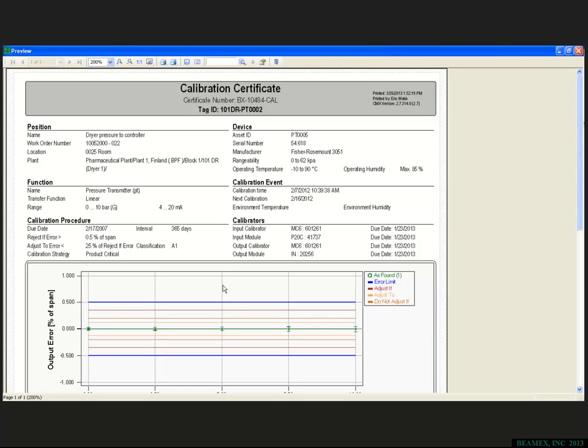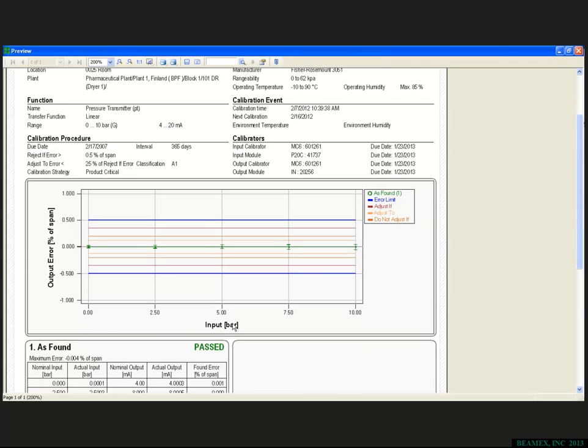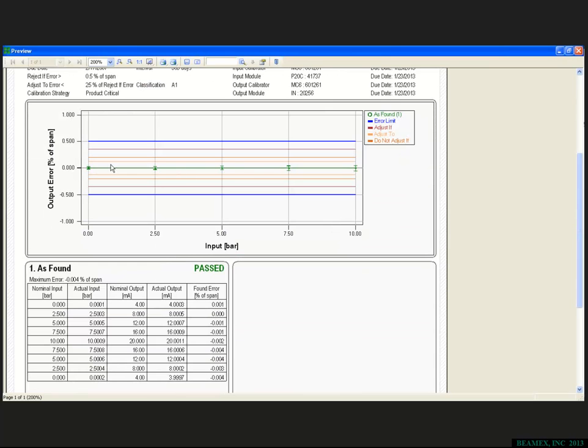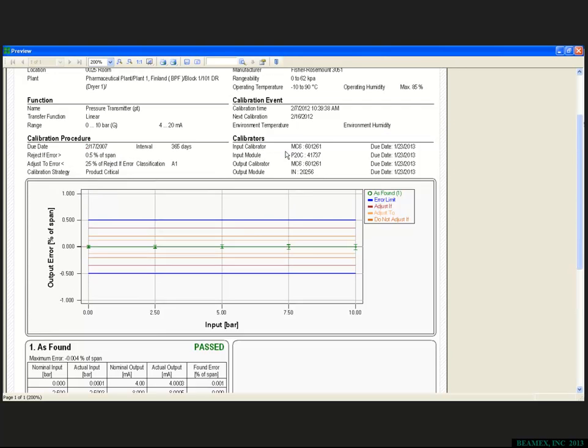So if we were on a 6-month calibration interval and over an 18-month period, which would be 3 calibration cycles, it met all of its criteria each and every time, then we could increase that calibration interval from 6 months to 9 months. The example that I'm showing you right now is just a standard calibration certificate. And what it shows you is all the information that I talked about earlier, as well as the calibration procedure. And then it gives you a graphical and a numerical view of that particular asset. And as you can see up here, that unit passed.